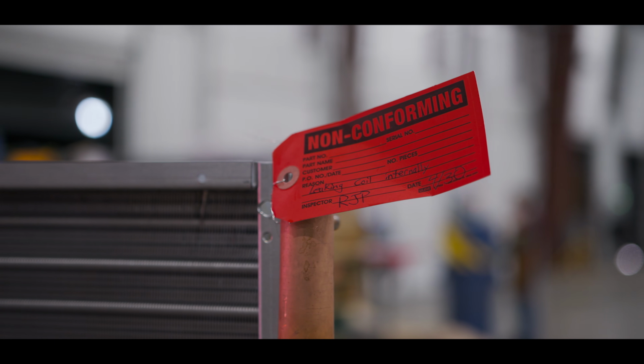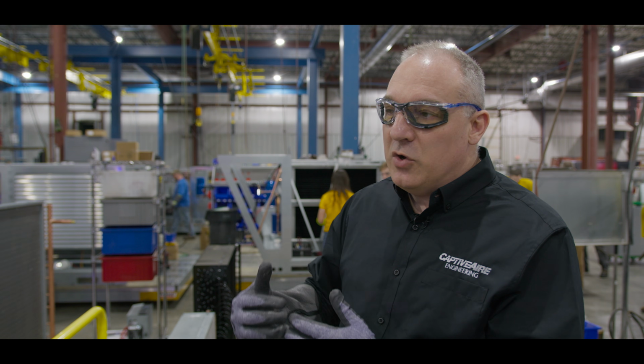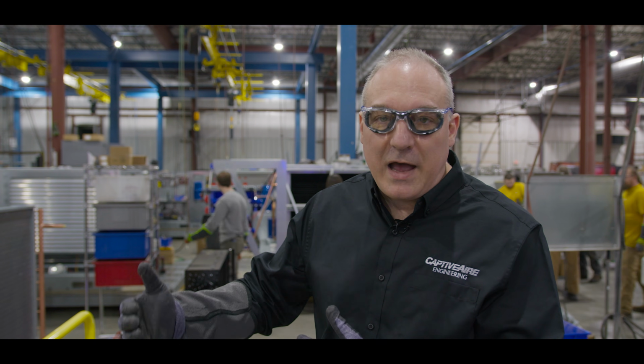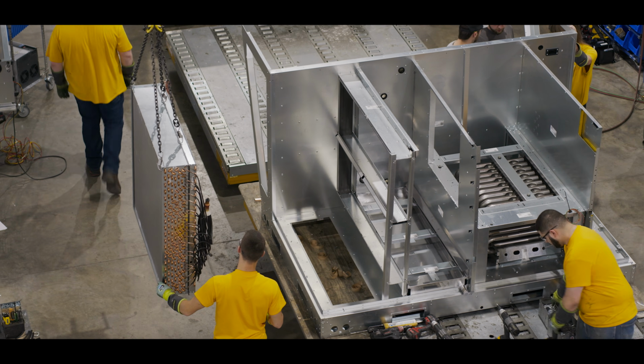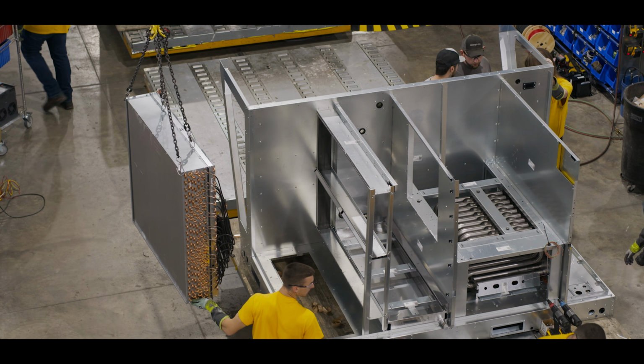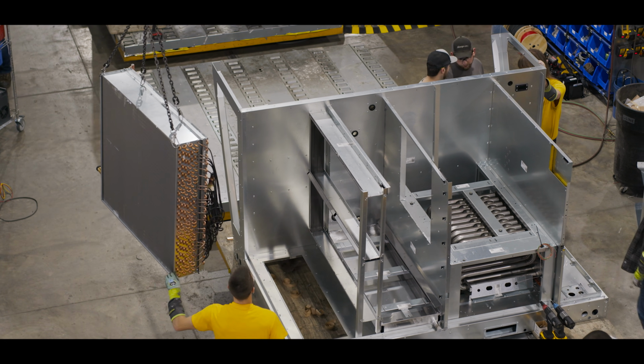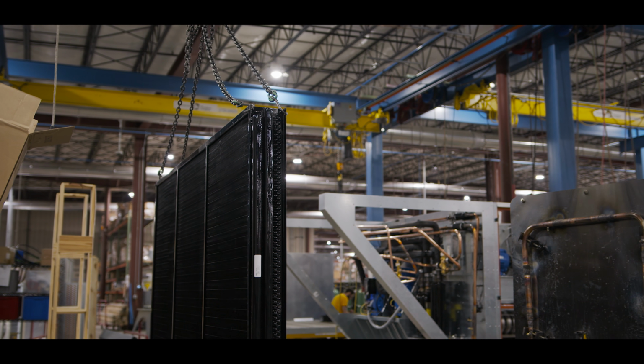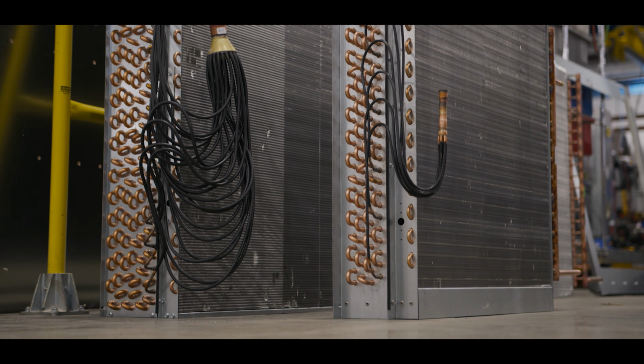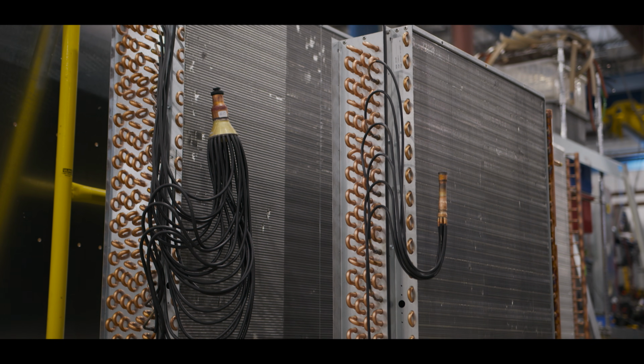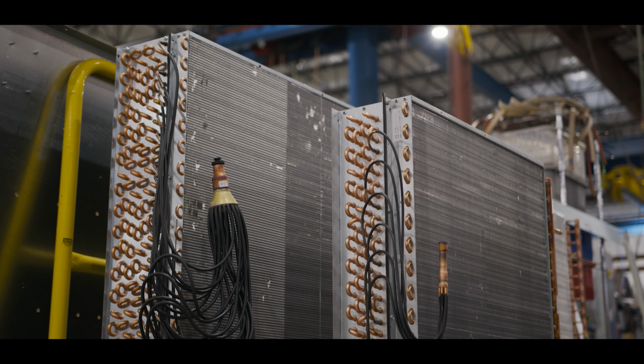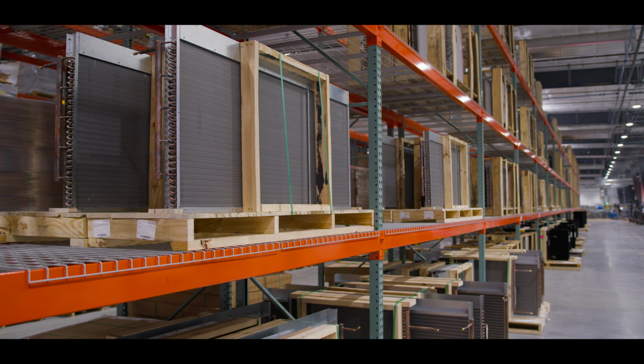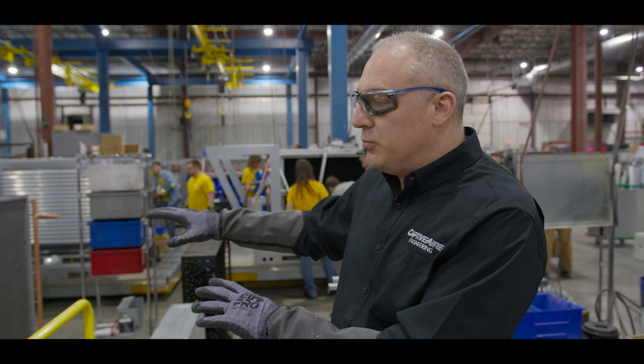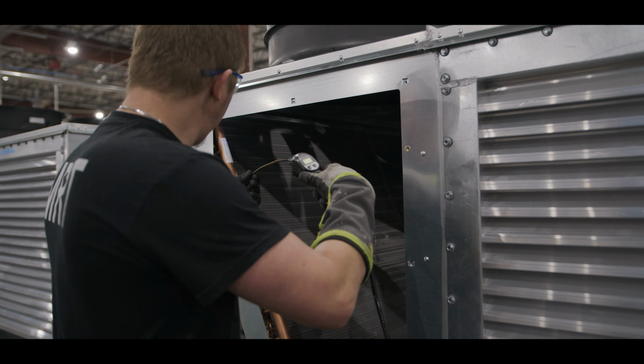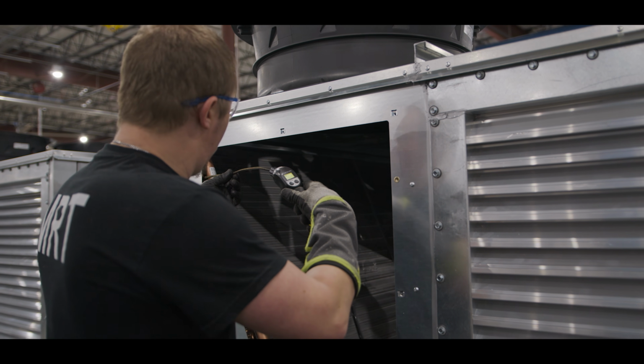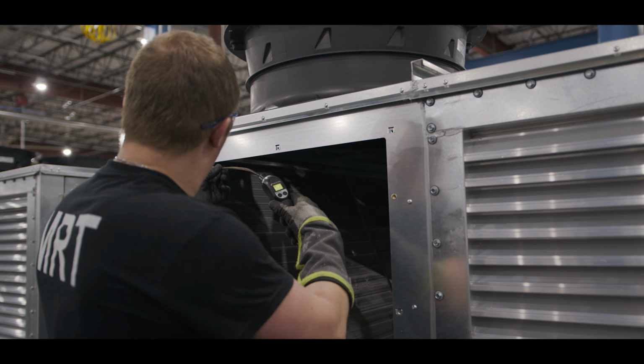These are a critical component to us, so we want to make sure that if we do have a leak, we identify where it's happening, what process is causing that leak, and it's a way for us to grade supplier quality as well. If we detect X% of coils from one supplier is much higher than another supplier, we know to shift that volume away or issue corrective actions to the supplier causing those issues. Not only do we check pressure in the coils from the supplier, but we also check downstream and inside the total system on 100% of units.